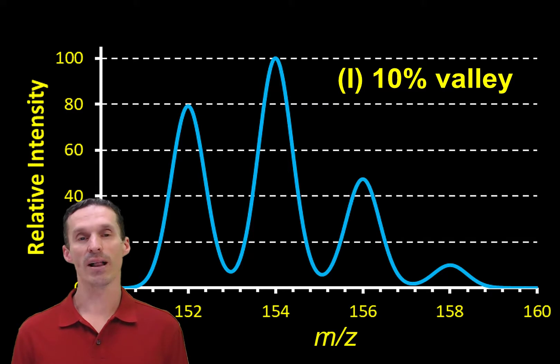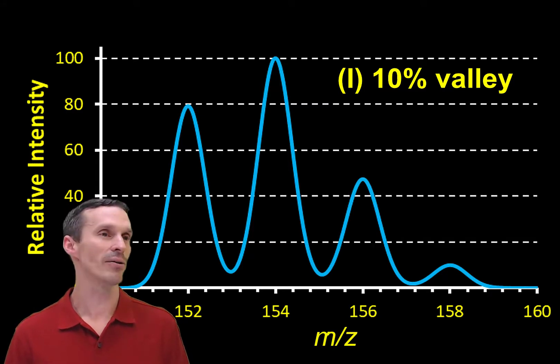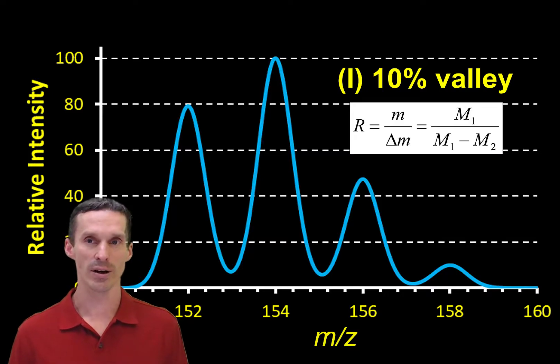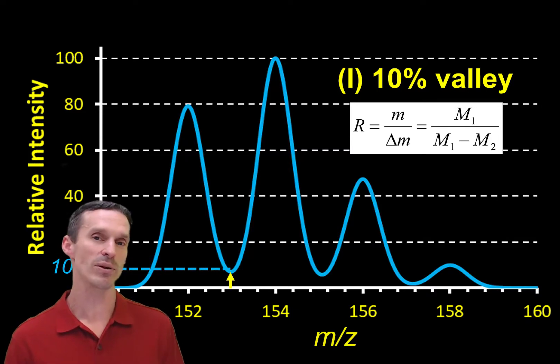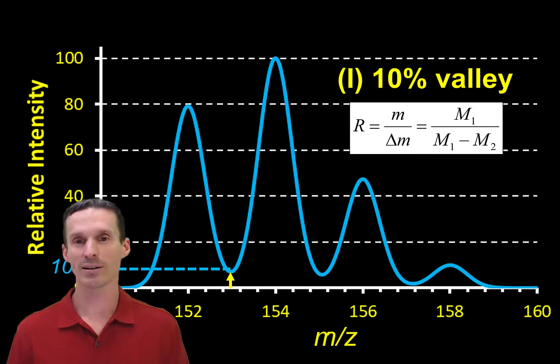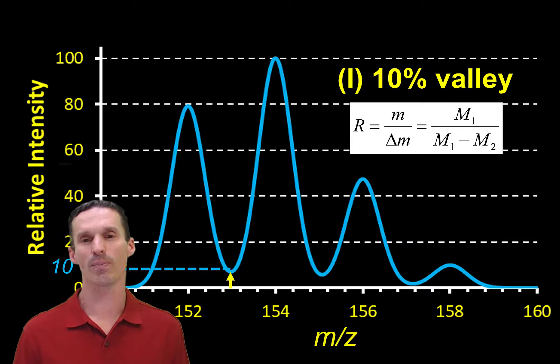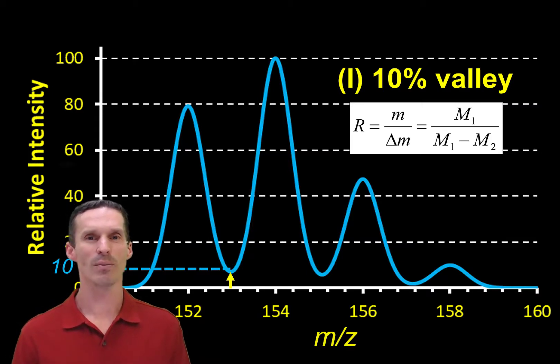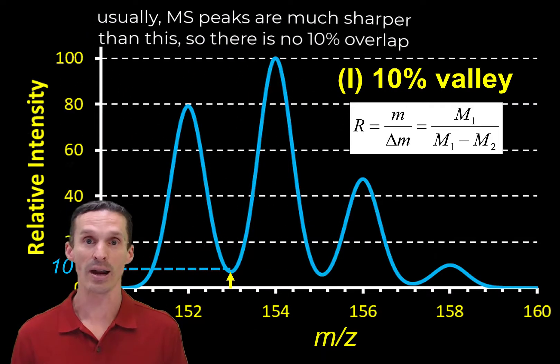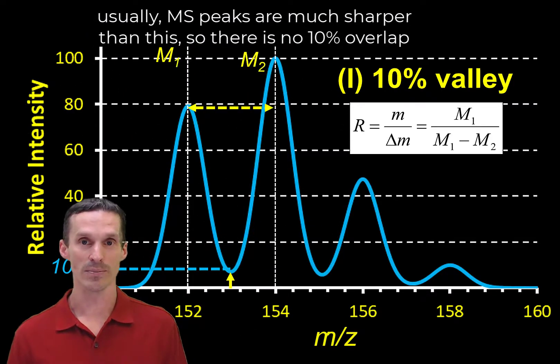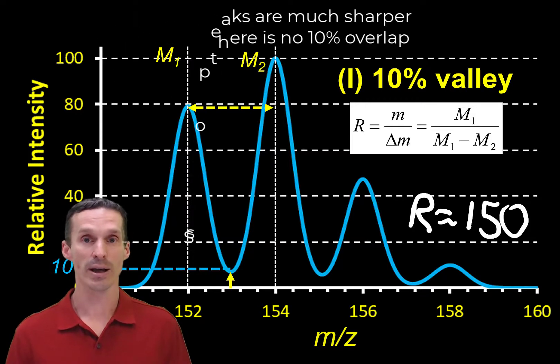The first one is the 10% valley definition. I'll be honest — I don't even like this definition. Very few people use this term when quantifying resolution. The situation depends on having overlap between two adjacent peaks, and technically the two peaks should be separated by one mass unit, though here they're separated by two, so this doesn't really apply. What you would need to do is find the case where they exactly line up at 10% — good luck with that — and then run it through the equation.